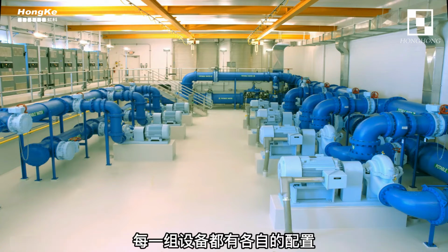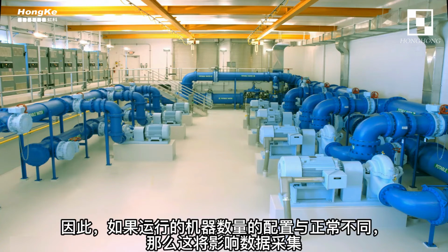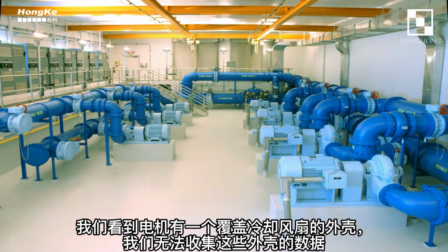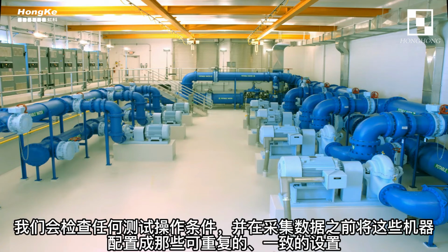We know each side feeds its own common header, so if the configuration of number of machines running is different from normal, then this would impact the data. We see the motors have a bell housing covering a cooling fan. We cannot collect data on these housings. We would review any test operating conditions and configure these machines into those repeatable, consistent lineups before collecting data.